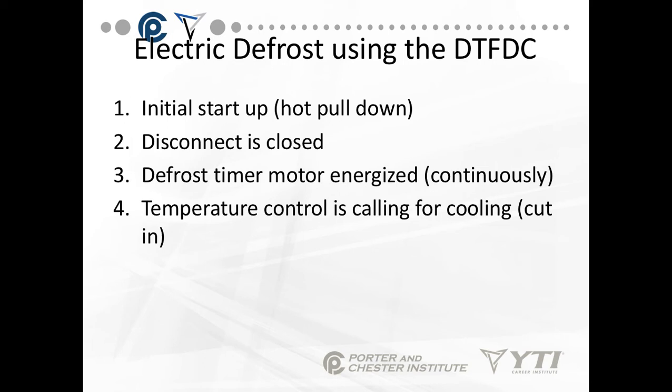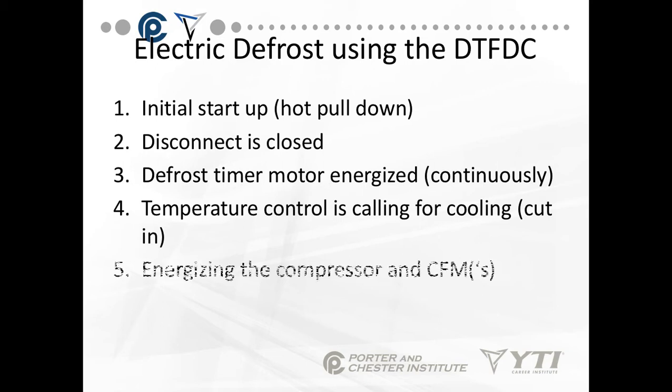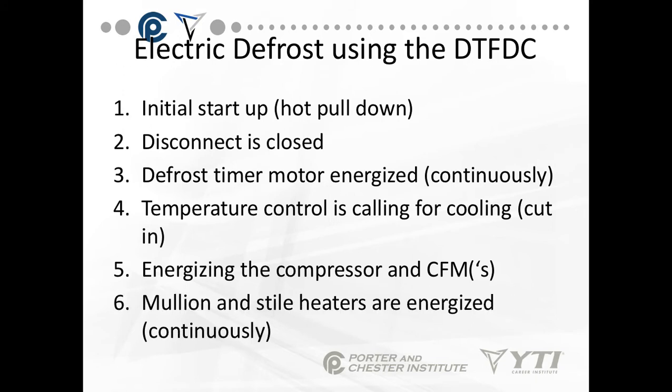That's the cut-in temperature. Cut-out means it's satisfied and not calling anymore. At cut-in, we energize the compressor and the condenser fan motors. The mullion and stile heaters are energized. When we're talking about mullion and stile heaters, these are the heaters that keep the surrounding areas of the doors free from frost.